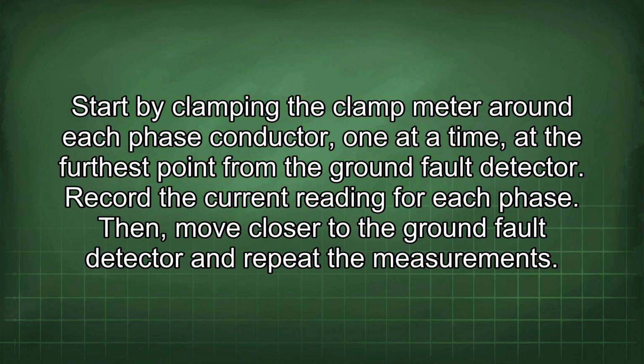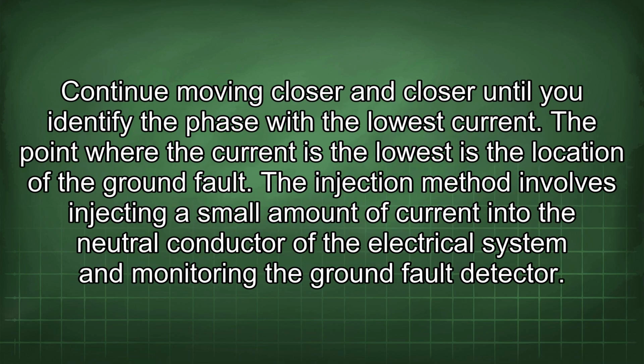Start by clamping the clamp meter around each phase conductor, one at a time, at the furthest point from the ground fault detector. Record the current reading for each phase. Then, move closer to the ground fault detector and repeat the measurements. Continue moving closer and closer until you identify the phase with the lowest current. The point where the current is the lowest is the location of the ground fault.